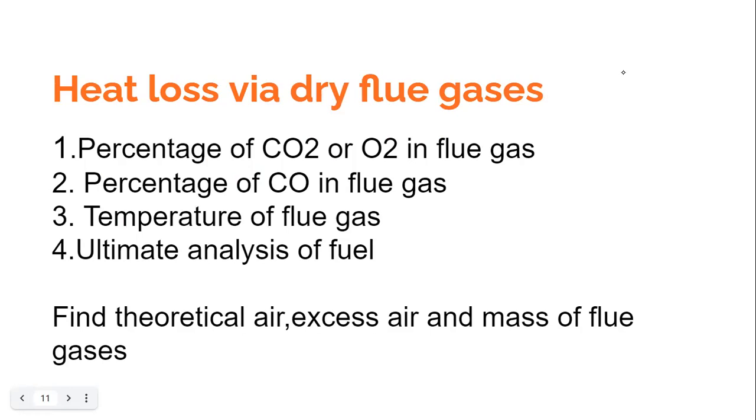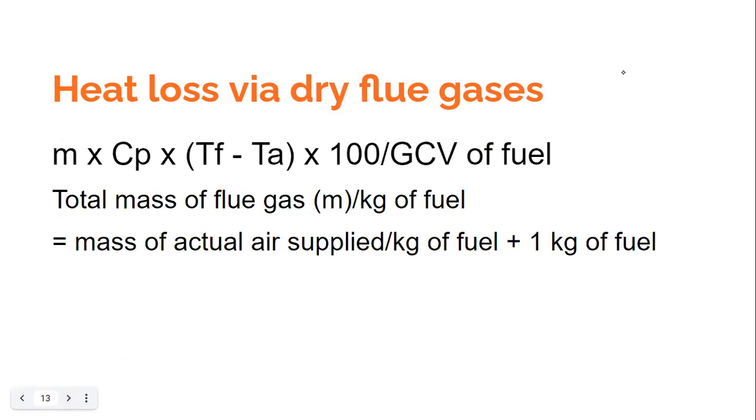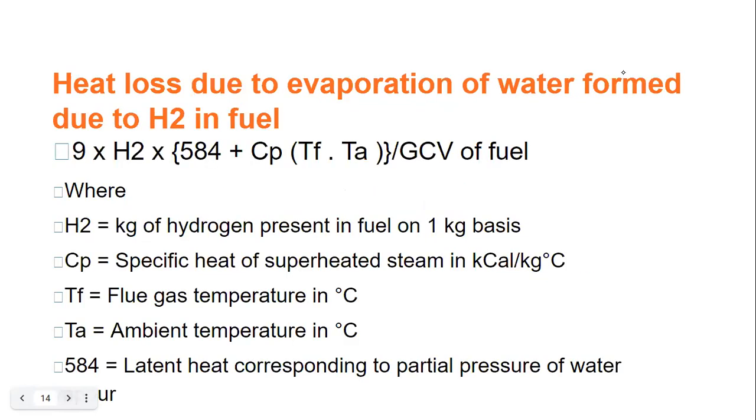This slide gives you heat lost via the dry flue gases, and for that we need to estimate the theoretical air required, the excess air required, and the mass of flue gases. This is one conversion formula which we talked about, and this is the proper expression for the flue gases heat loss.